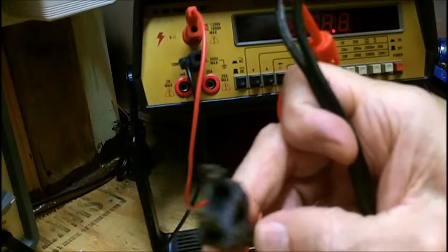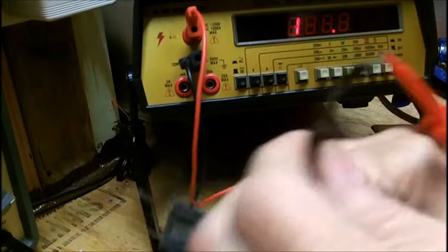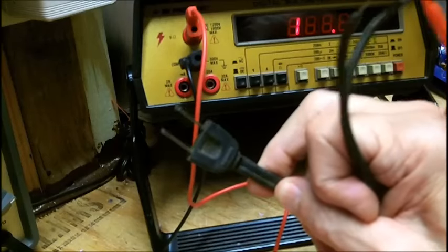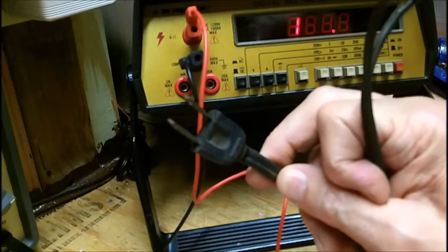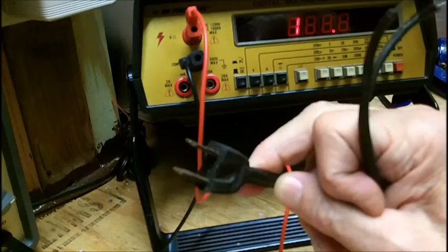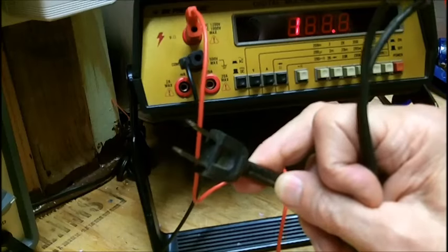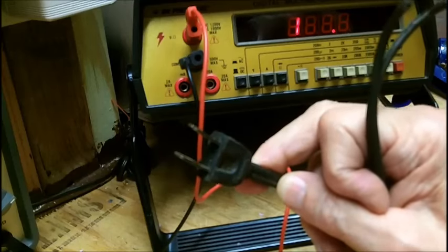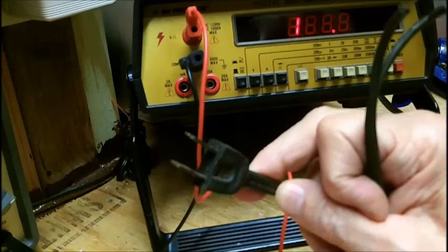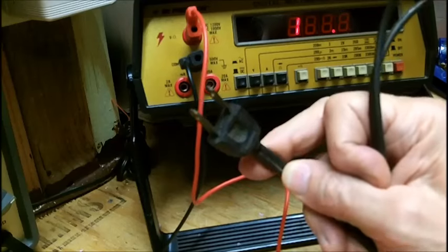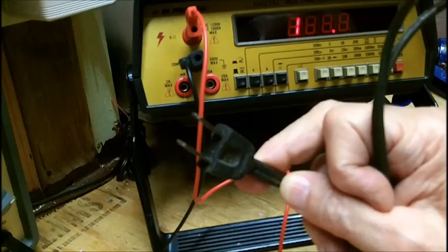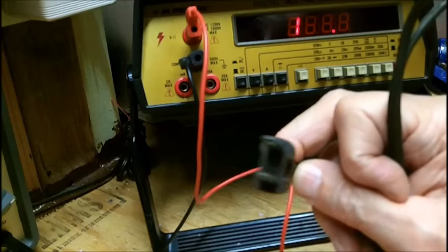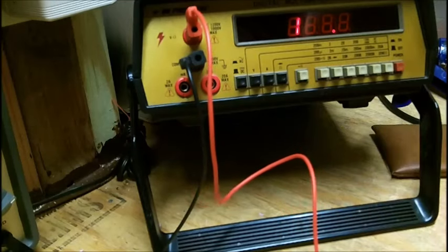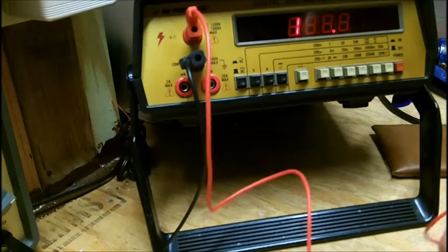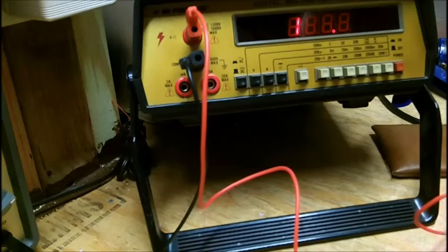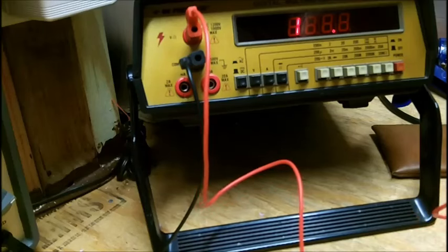Alright, what I'm going to read now is line voltage, using both meters, the Fluke 73 and this one, at the same time, since we're measuring line voltage so it shouldn't matter. You wouldn't want to do this with resistors or sensitive low voltages by having 2 meters connected at the same time to the same source, because one meter will pull on the other and affect the readings, but we're talking line voltage now.